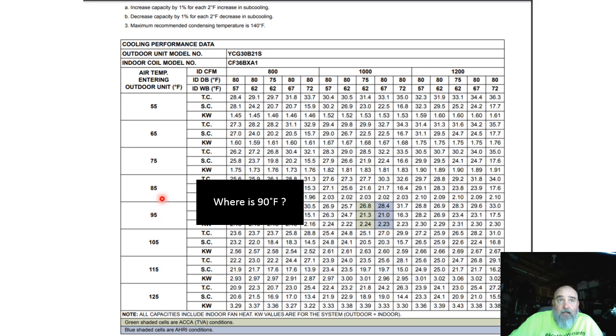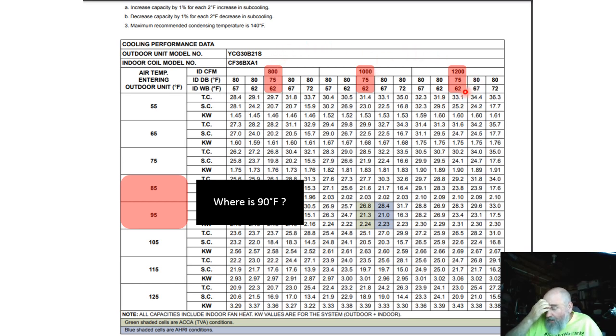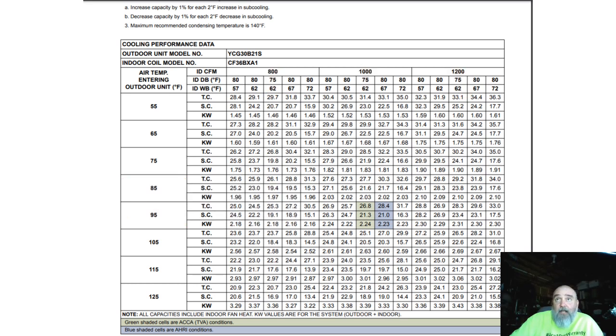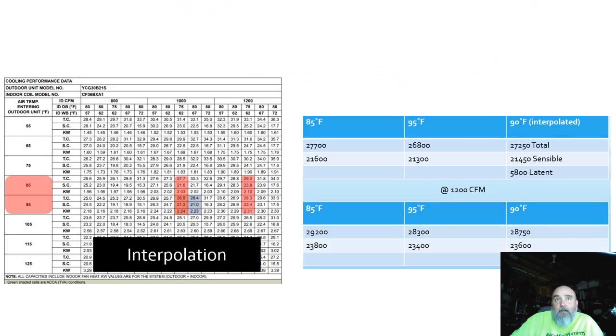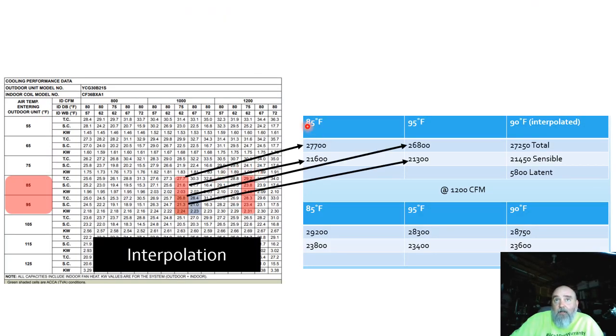90°F isn't on the equipment table I randomly selected off the internet, so what we do is called interpolation. We could potentially be selecting our equipment to run at 800, 1000, or 1200 CFM. To interpolate, we take the 85°F and 95°F data and combine it — we took our total and sensible capacities at 85 and 95, added them together, and divided by two. So here's our total capacity at 90°F, our sensible capacity at 90°F, and we solve for latent by subtracting sensible from total.